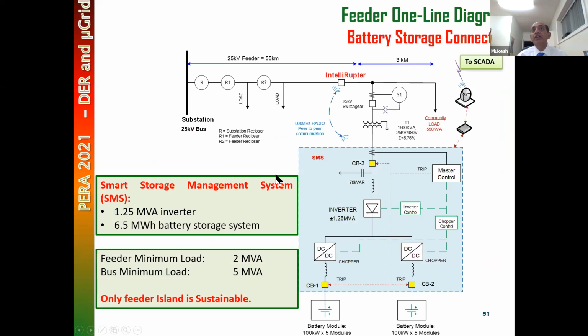Here it is. This is a one-line diagram of the feeder, the 60 kilometer long feeder I told you about, and this is the battery. These are two batteries, and together the inverter is 1.25 MVA. The battery storage is 6.5 megawatt hours, which can supply this community for an extended period of time. It can supply at least 8 to 10 hours of power to this community, by which time the crew can come and restore the power in most cases. The minimum load on the feeder is 2 MVA. There's some load here, some load here, some load here, and this load is about 500 kVA, but the total feeder minimum load is 2 MVA.